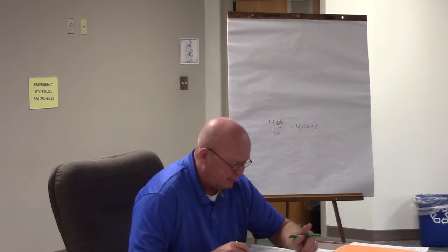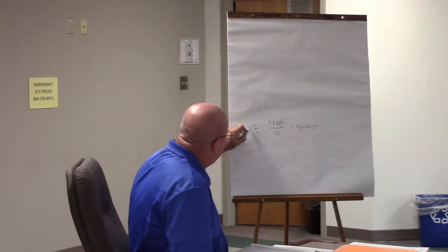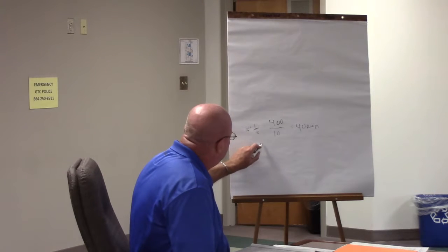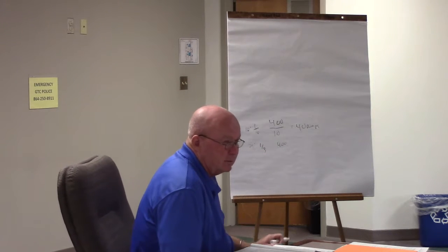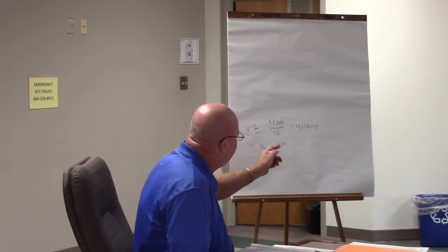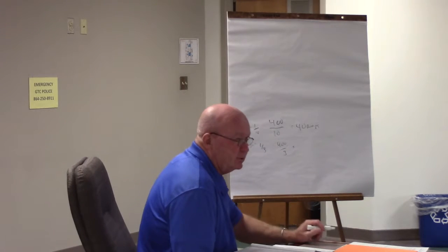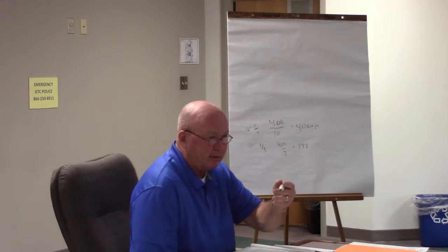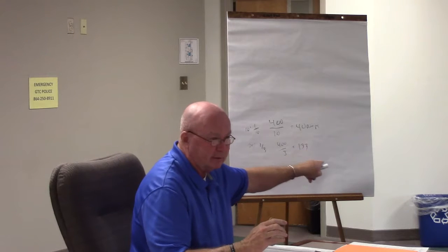Now here's where it's going to be different. Read bullet number 2. The tap conductors must be rated at no less than 1/3 the capacity of the overcurrent device protecting the feeder. So 10-foot rule is 1/10. All right. 25-foot rule is how much? 1/3. So if we had this 400 amp illustration, what would we do to find the minimum? If we divided by 10 earlier, what would we divide this by? 3, wouldn't we? 400 divided by 3 is how much? 133. And so then if we were to go to our 310.15(B)(16), we would see the wire size couldn't be any smaller than 133 amps.